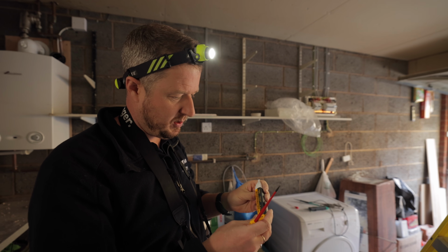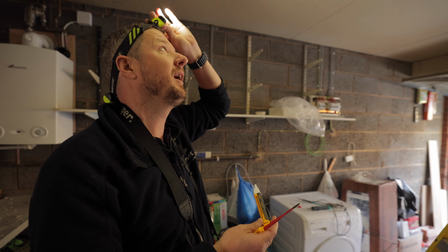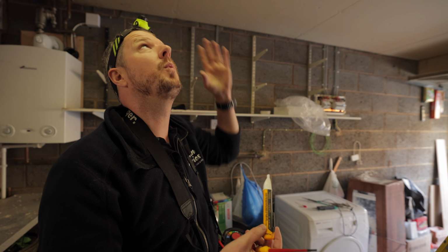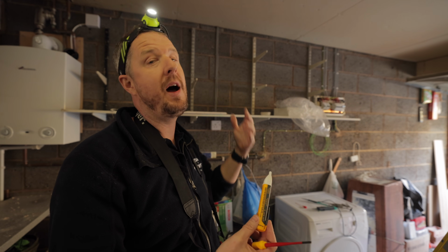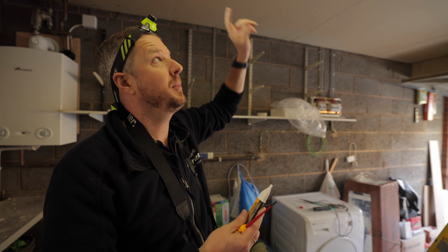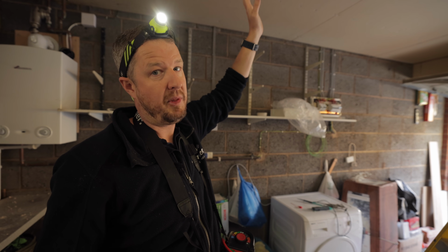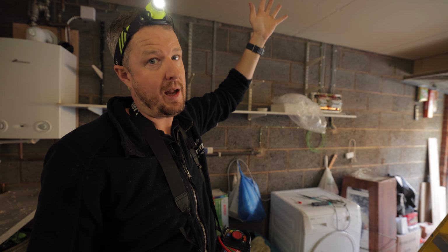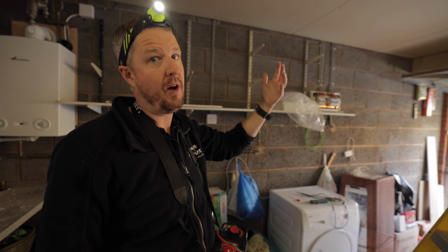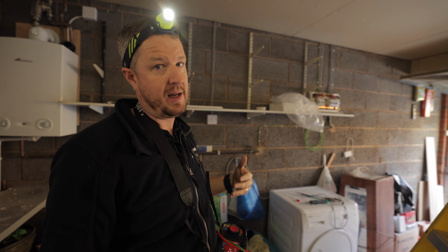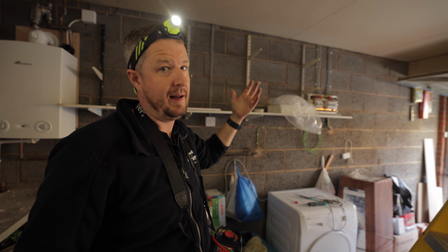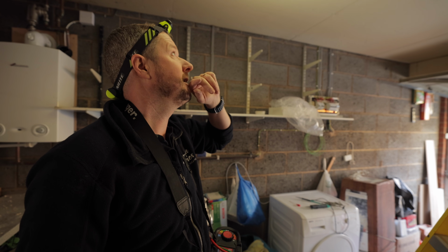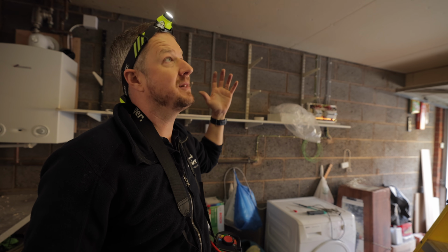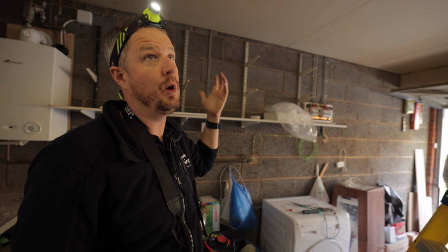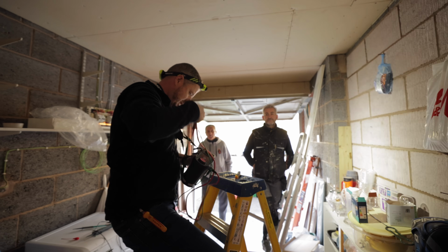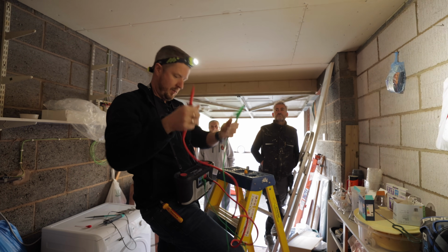So we're not just talking trickle voltage here, we're talking a serious amount of voltage, which is what I'm so worried about. That's higher than touch voltage, which means that in theory, if somebody touches this ceiling and something else that's earthy, they could get a shock, because anything more than about 50 volts AC, the human body will conduct that and you'll get an electric shock. So we do need to figure out what this is doing, because it is genuinely dangerous and could pose a risk to life. Let me test it with this and see if there's anything coming up with this at all.